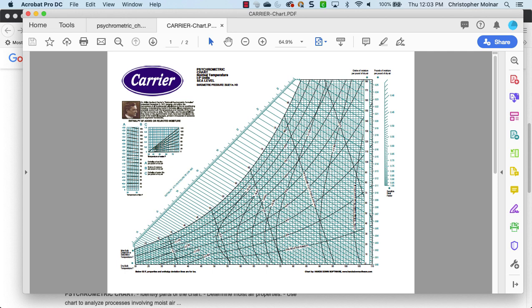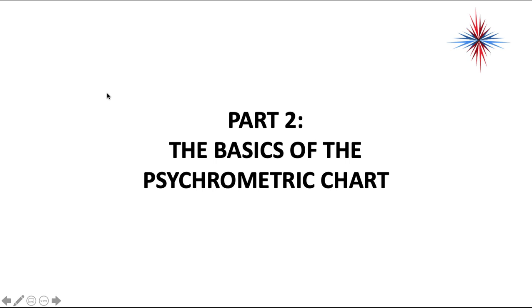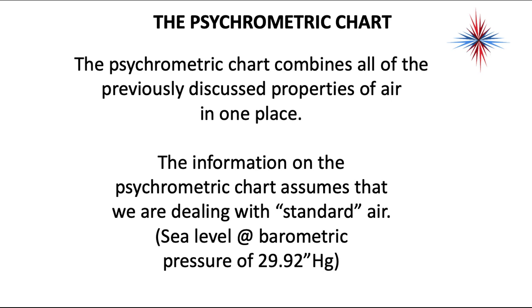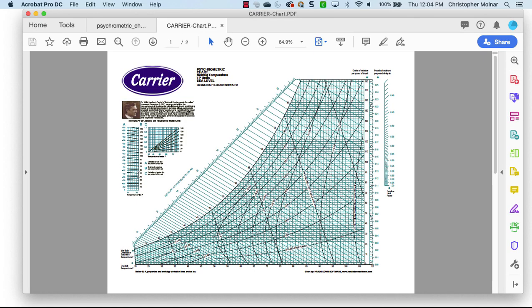The psychrometric chart is a chart that combines all of the previously discussed properties from part one of our videos — properties of air — in one place. The information on the psychrometric chart assumes that we are dealing with standard air, meaning sea level at barometric pressures of 29.92 inches of mercury. All the information is here in one place: specific air, wet bulb, dry bulb, relative humidity — everything else is here on one chart.